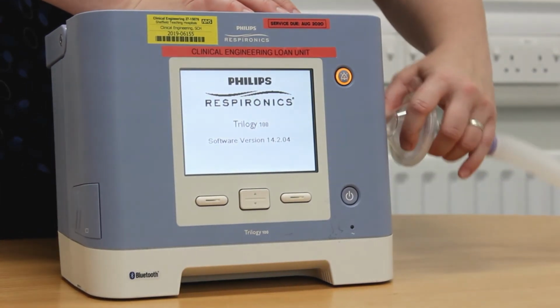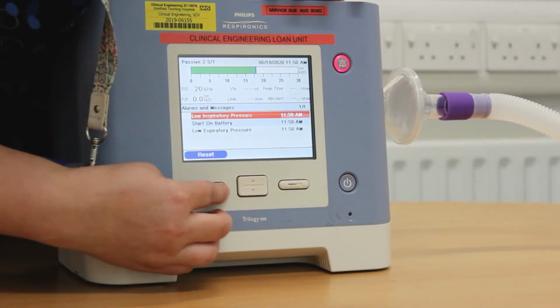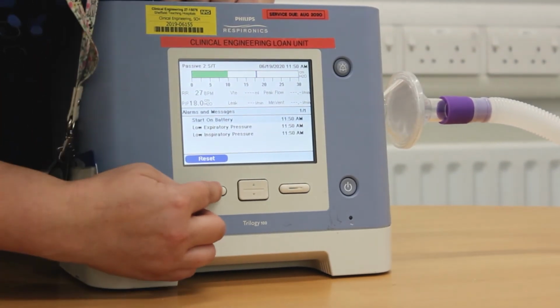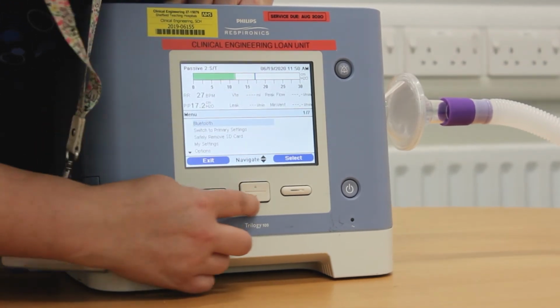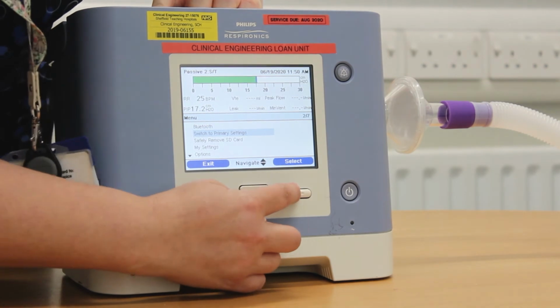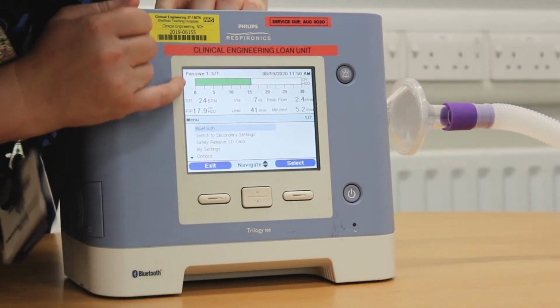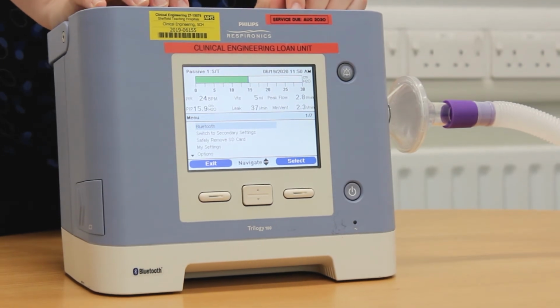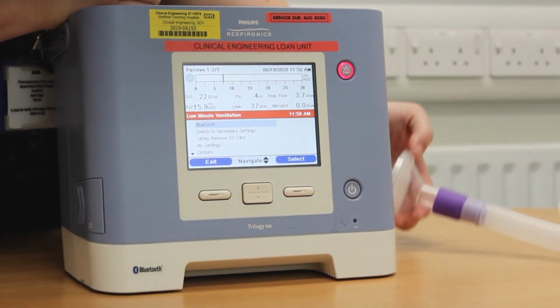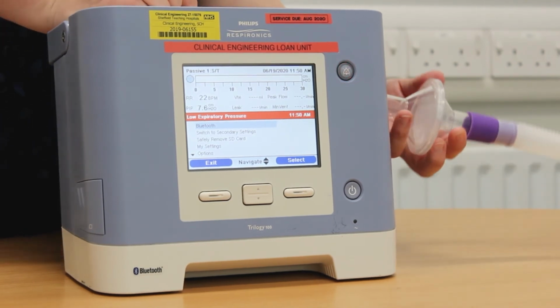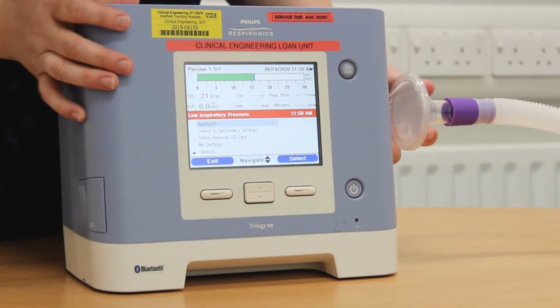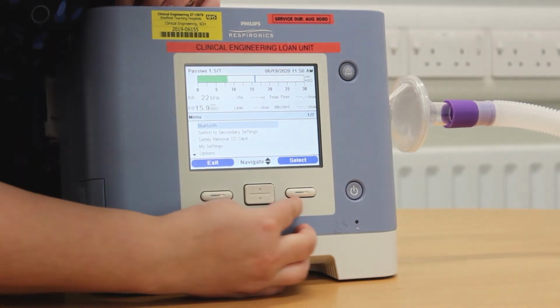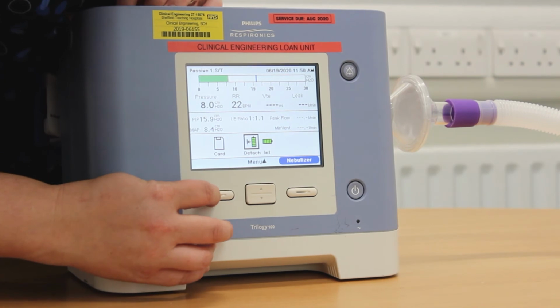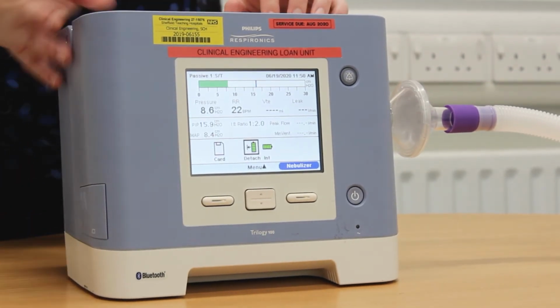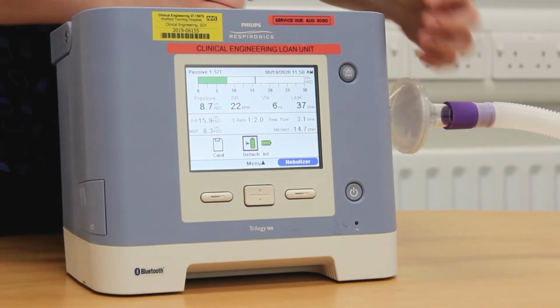If I want to switch between settings while the child is on the ventilator, I can do so. I must make sure that no alarms are happening, so I reset them all, press menu, switch to secondary settings and confirm. You will see at the top it changes. Anytime an alarm is going off, you will hear a loud noise and a red bar will appear to tell you what alarm is happening. If nothing else is on the screen, I can press reset once I've corrected the alarm and it will go back to the main menu.